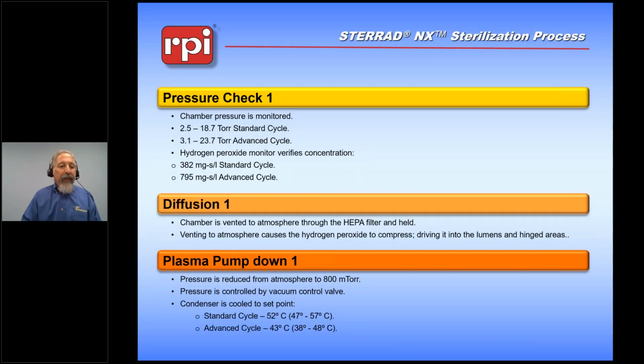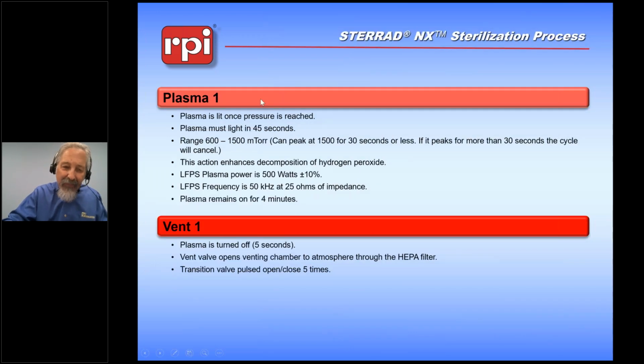Okay, pressure check. So now that we've put our peroxide into the chamber, we want to make sure that the pressure has not changed or reacted with the transfer. We keep a control over the pressure or the vacuum in torrs between 2.8 and 18 torr, and that should produce a concentration in the lumen and the various hinges of approximately 380 milligrams per standard liter of airspace, what would be within the chamber. We allow that to sit within the chamber to diffuse in.